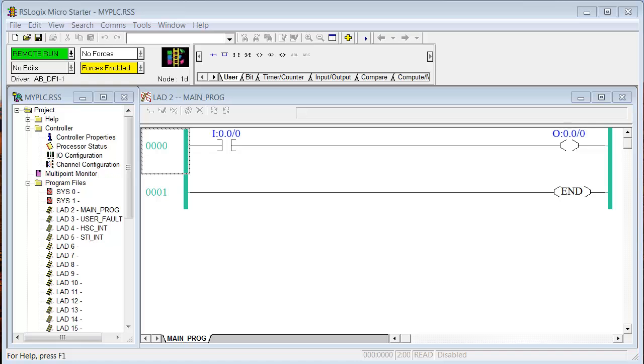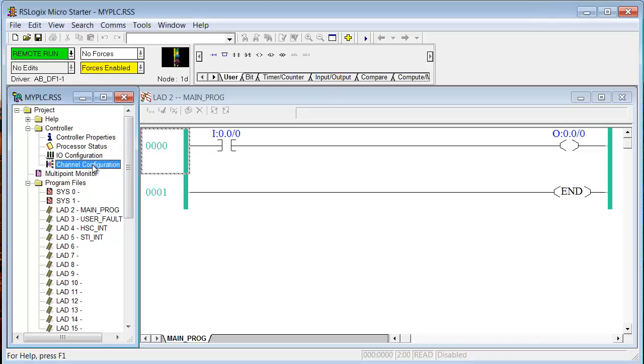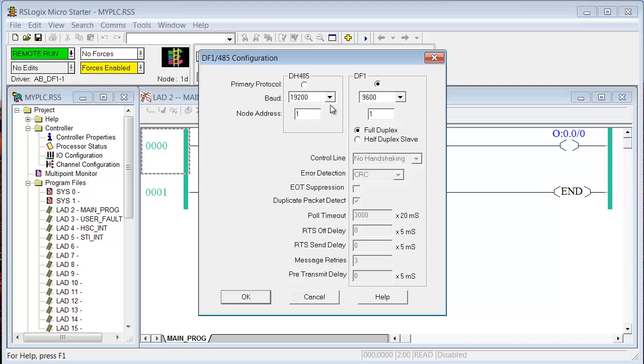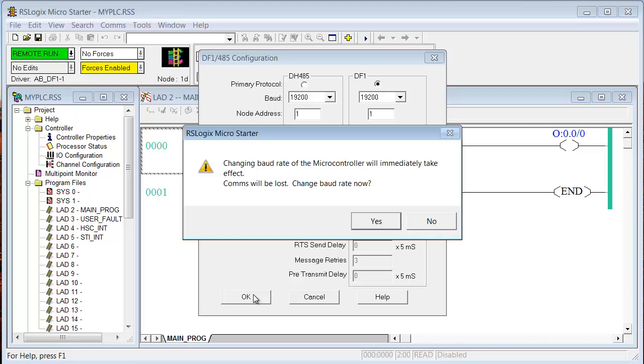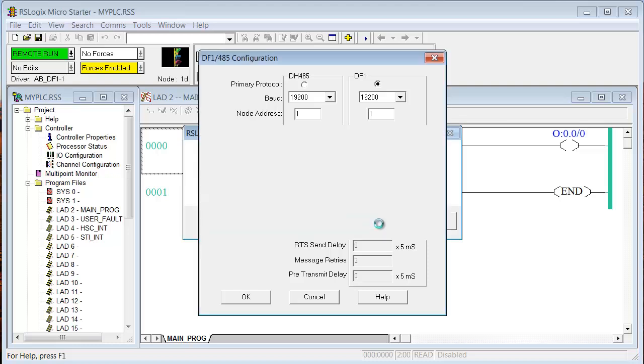I opened up RSLogix Micro Starter again and went online. You can see we're in the remote run mode. I wanted to demonstrate something that I mentioned earlier and I have mentioned in other presentations. Now we know that the driver, RSLinx driver, was auto-configured, I think, for 9600. So if we go to Channel Configuration, we can see here that the driver is configured at 9600. Now I'm going to show you what happens when you change this to 19.2 online. I'm going to say OK. Now remember that right now we're online. RSLogix Micro Starter is communicating with this processor through an RSLinx driver that's set at 9600. I'm telling the processor right now that you're 19.2. Changing the baud rate of the microcontroller will immediately take effect. Comms will be lost. Change baud rate now? Yes. OK. So it kicked us offline. Now we can't go back online.